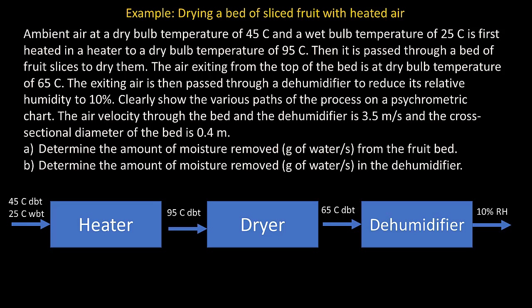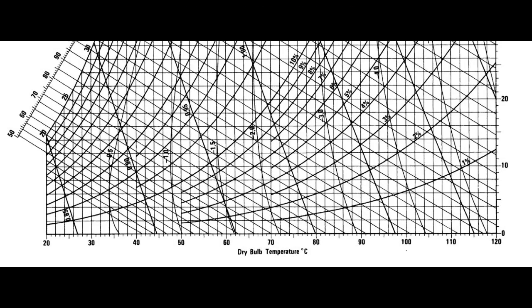Now let's look at a psychrometric chart and plot the various points on the chart. First we identify the dry bulb temperature of 45 degrees Celsius, then follow the lines both for the wet bulb and dry bulb and they will meet at point A. Point A represents a dry bulb temperature of 45 degrees Celsius and a wet bulb temperature of 25 degrees Celsius — this is the condition of the ambient air.